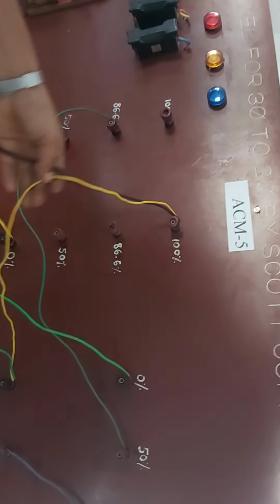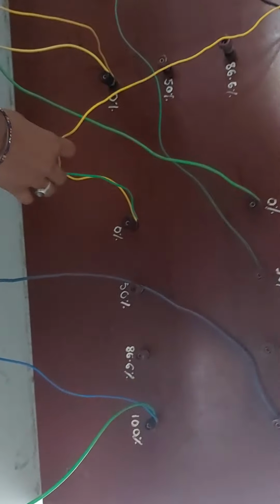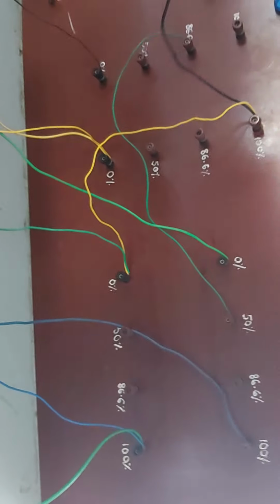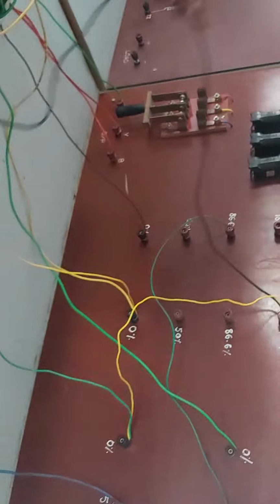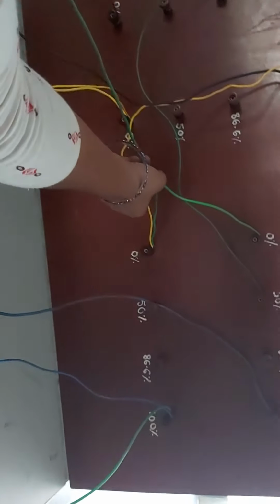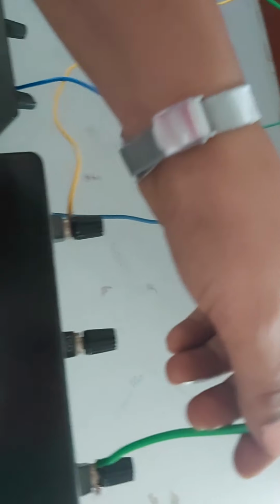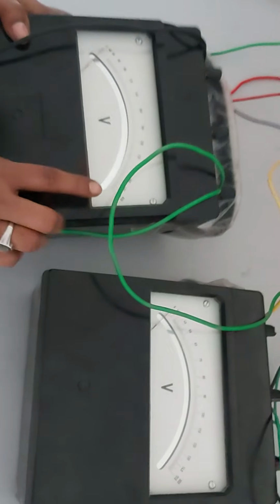and from the primary side of the main transformer, 50% will be connected to the teaser transformer 86%, and the 100% of the teaser transformer will be connected to one secondary 0% of the main transformer, and one wire will be connected across another voltmeter's second terminal. Next we will take another wire that will be connected between the voltmeter and 0% of the secondary of the main transformer. And now from the main transformer, from the 100%, we are taking two wires. One wire will be connected to a voltmeter's second terminal and one wire will be connected to another voltmeter. So these two measure the voltages of the main and teaser transformers, and this voltmeter measures the three phase AC supply.